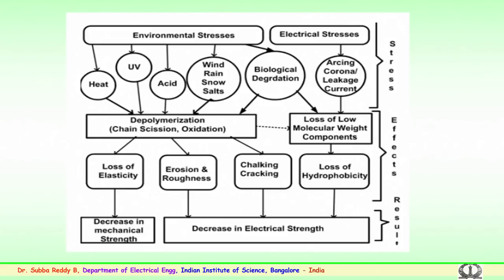So, the consequence of these various environmental stresses: temperature, either heat or very low temperature, will cause problems. Ultraviolet radiation could come from the sun or from the corona of the hardware or the corona control rings of the insulator string. Chemical stresses could come from the acid rain composition or from industries nearby to the transmission system. These stresses could cause depolymerization. There could be chain scission, breakage of the bonding of the material, and oxidation could happen.